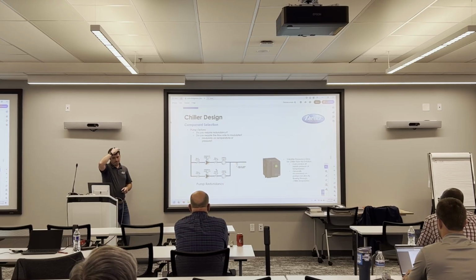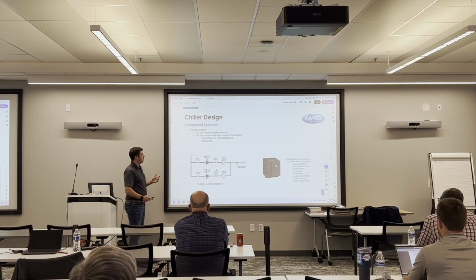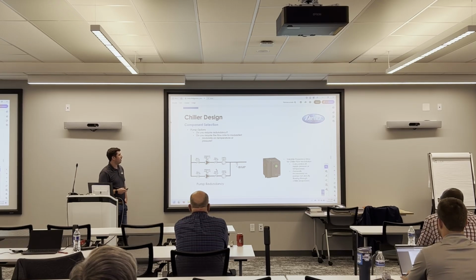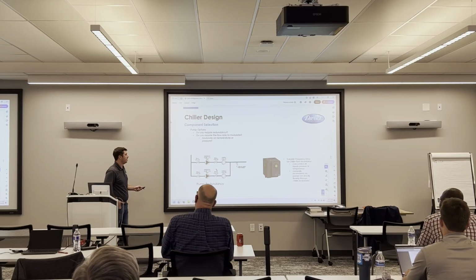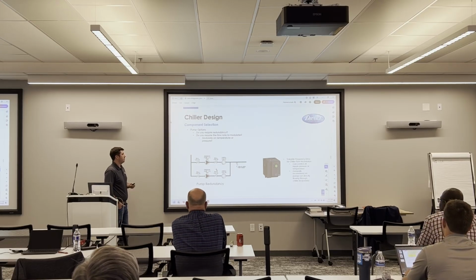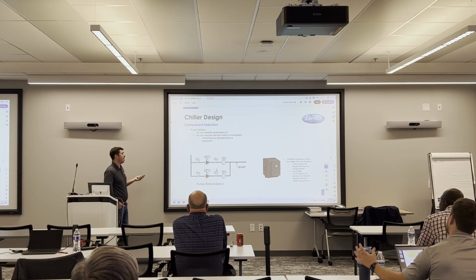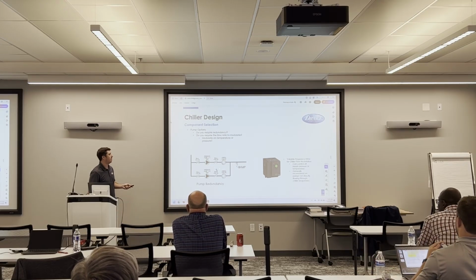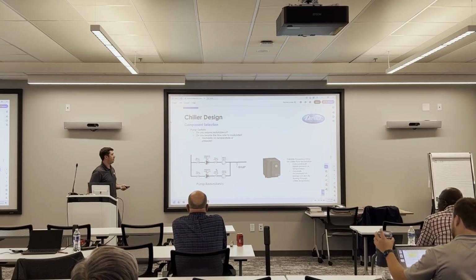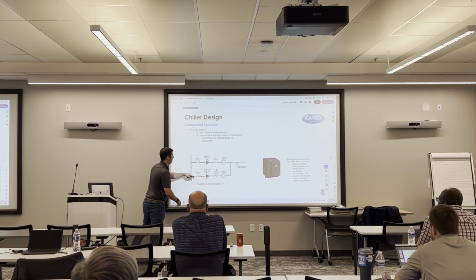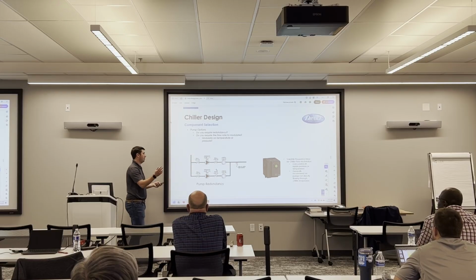All right, and then some pump options that we can ask about when we're doing a quote. Are you going to require any sort of redundancy? Down below is just an example of redundancy. If they have a pump failure, you don't want to be dead in the water if you can't deliver the flow to your process loop. So maybe you add a secondary pump to turn on if we have some sort of pump failure, or maybe just for general service. If I put a filter in line with these pumps, and the filter gets clogged with the one pump, well then I can just valve off that pump, turn on the other pump, clean my filter, put it back into operation, and on with that.